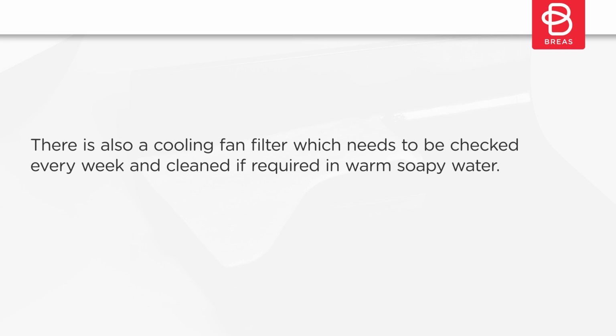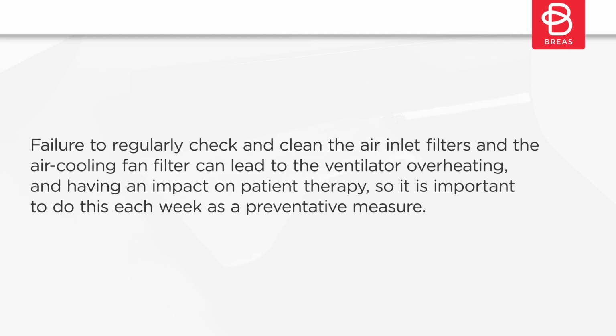There is also a cooling fan filter which needs to be checked every week and cleaned if required in warm soapy water. Failure to regularly check and clean the air inlet filters and the air cooling fan filter can lead to the ventilator overheating and having an impact on patient therapy, so it is important to do this each week as a preventative measure.